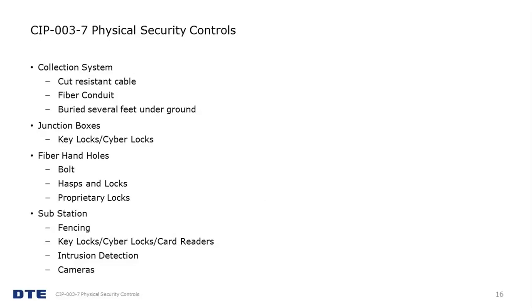One thing to think about with fiber conduit - a lesson learned for us - is that if your fiber runs above ground, put it high enough that somebody can't just walk up and cut it. After completing a couple of wind parks, we found some fiber had been run only 4 or 5 feet in the air in places, where anybody could walk up and cut it. So if it's above ground, get it as high as you can, so at least someone would need a ladder.